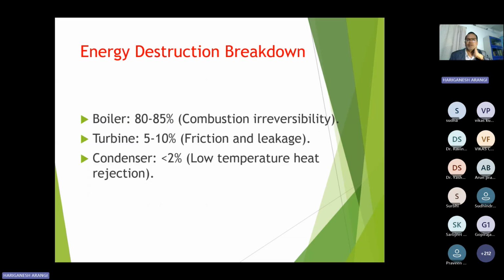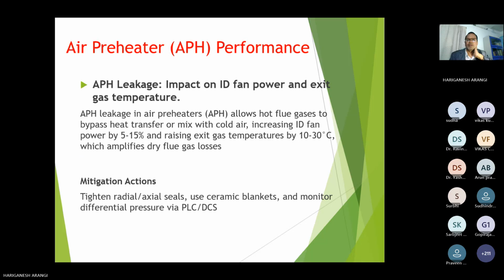This is how the energy destruction breaks down: in the boiler 80 to 85%, the turbine 5 to 10%, and the condenser less than 2%. Next comes the air preheater.